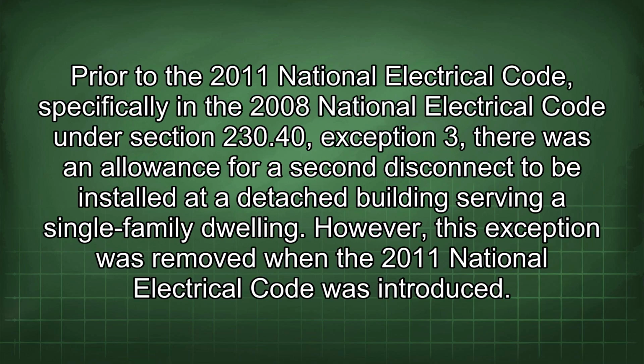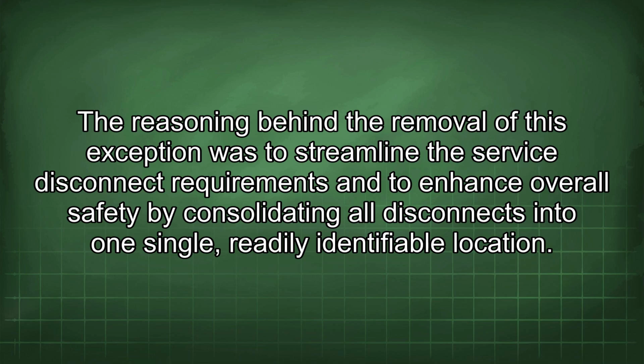Prior to the 2011 National Electrical Code, specifically in the 2008 National Electrical Code under Section 230.40, Exception 3, there was an allowance for a second disconnect to be installed at a detached building serving a single-family dwelling. However, this exception was removed when the 2011 National Electrical Code was introduced. The reasoning behind the removal of this exception was to streamline the service disconnect requirements and to enhance overall safety by consolidating all disconnects into one single, readily identifiable location.